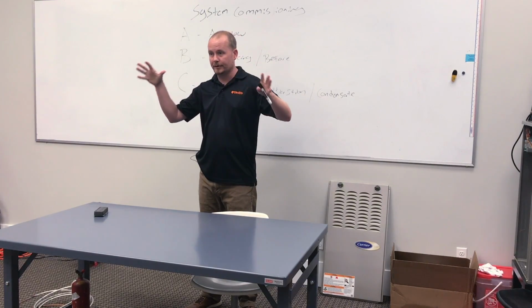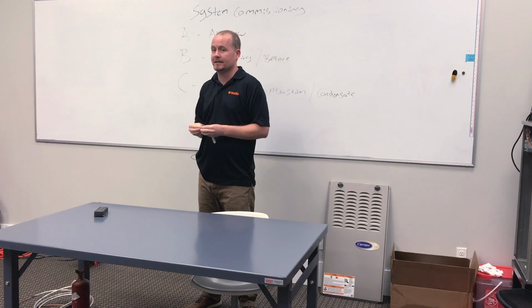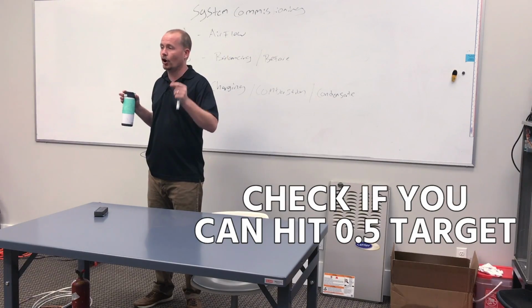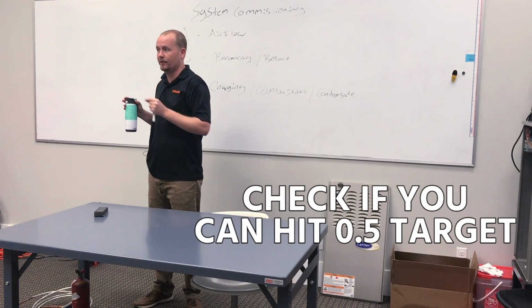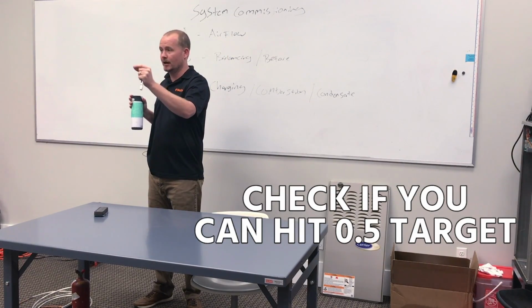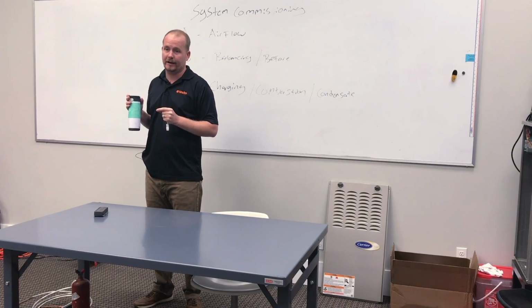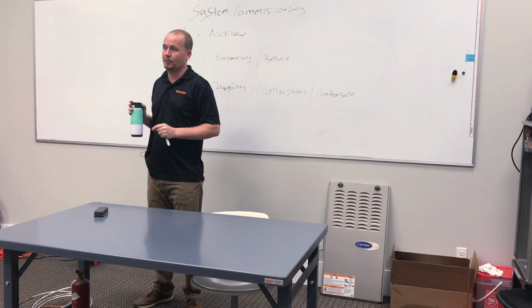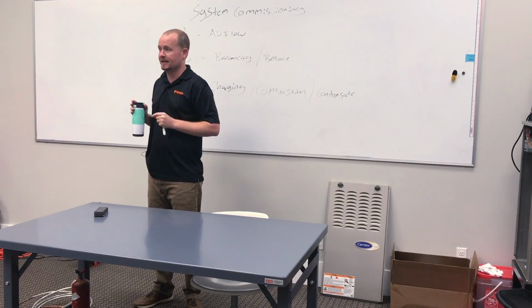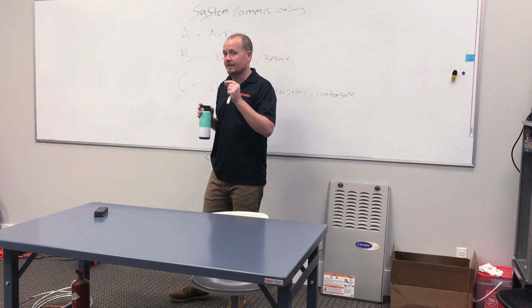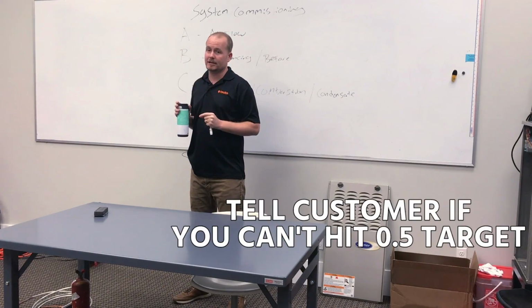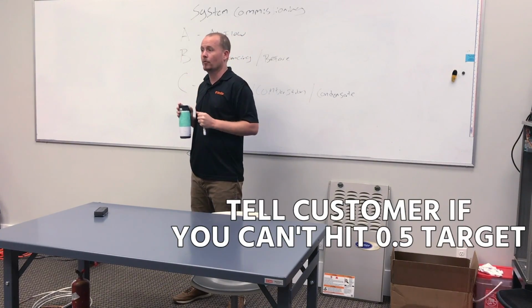Now, sometimes it can't be helped. You've got ductwork in between floors, you've got all that, but in the sales process, what should we do? What should we do if we go to a house where we know we're going to install this new unit and it's going to be over 0.5? We should always quote a job so that we can hit that 0.5 target. If we quoted a job and we cannot hit that 0.5 target, and we install it and we don't hit it, then we made a mistake in the sales process. Because at the very least, if we can't hit it, what we need to tell the customer is, it doesn't look like we're going to hit our 0.5 target.